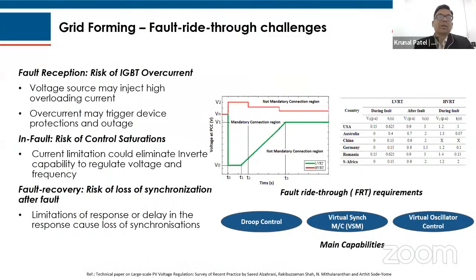Going to the next slide, I would like to explain the fault ride through challenges. In any microgrid scenario, faults generally happen, and these low voltage and high voltage faults can create a complete unbalance in the overall microgrid. How does this affect the grid inverter? Once a fault occurs, there is a risk of IGBT overcurrent, which may damage the complete inverter. The voltage source may inject a very high overloading current, and this overcurrent may trigger the device protection and cause an outage.